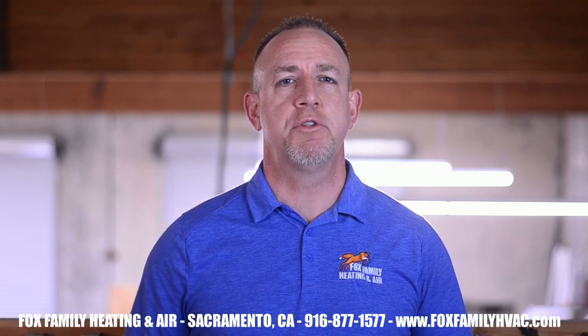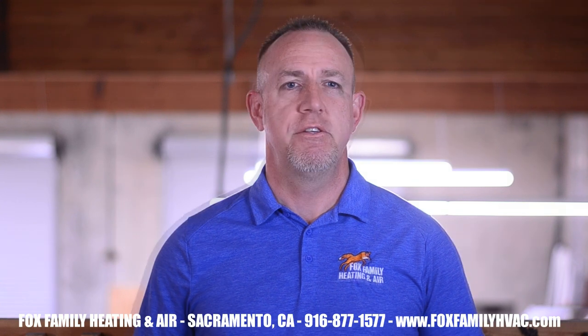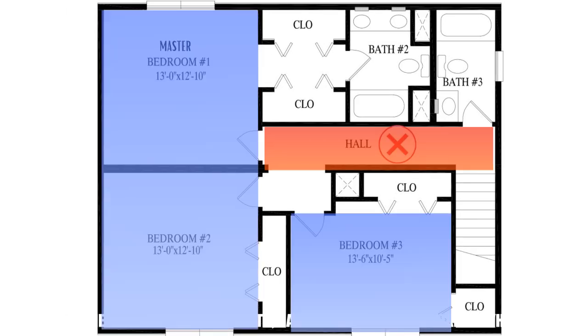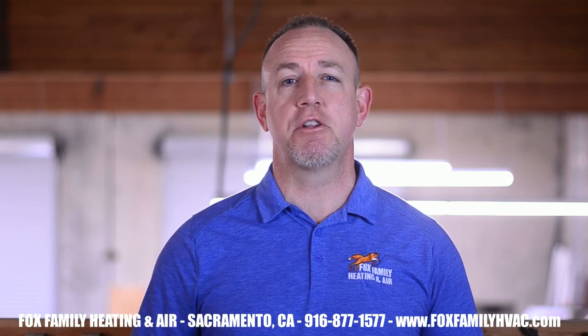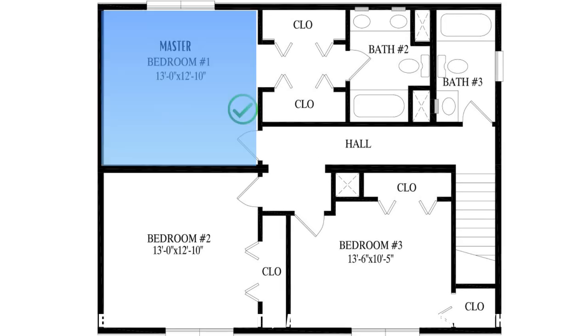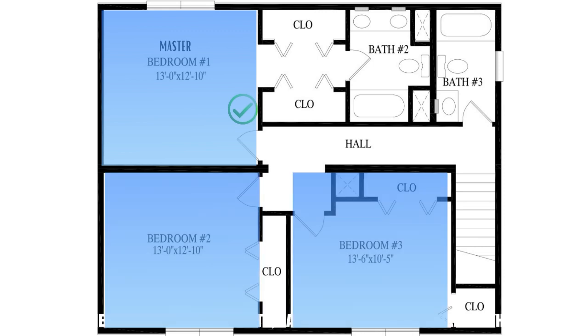In two-story homes that have two thermostats, one upstairs and one downstairs, you'll find that most families in my area of the country have the upstairs thermostat in the master bedroom. It's because the air temperature in the hallway upstairs can be different from the temperature of the air in the bedrooms, especially if the occupants close their bedroom doors at night. It's very likely that the most important room to control upstairs is the master bedroom. If the airflow in the other rooms up there is not sufficient, a little bit of air balancing in the ductwork will solve that problem — put an adjustable or manual damper in each duct upstairs so that you can dial in the airflow as you see fit.